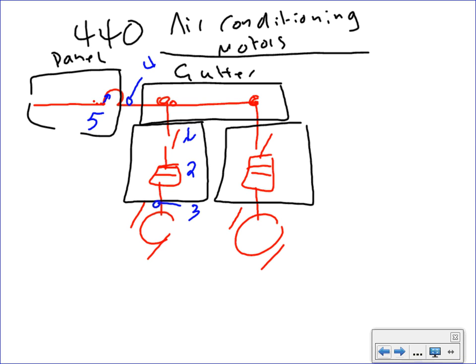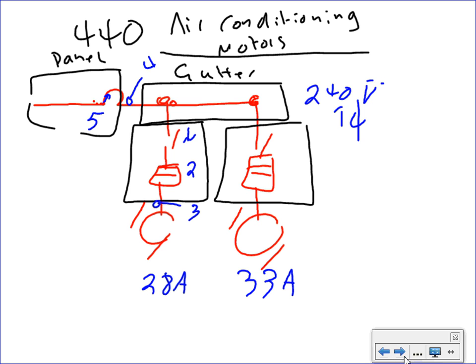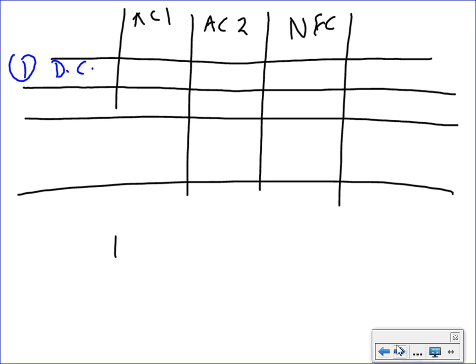This is a 240 volt system, the same thing, single phase. This equipment came up with 28 amps, and this equipment came up with 33 amps. 28 amps and 33 amps are on the nameplates. Okay, 28 amps and 33 amps, and 240. Everybody got that one? So remember, this is 28 amps and this is 33 amps.